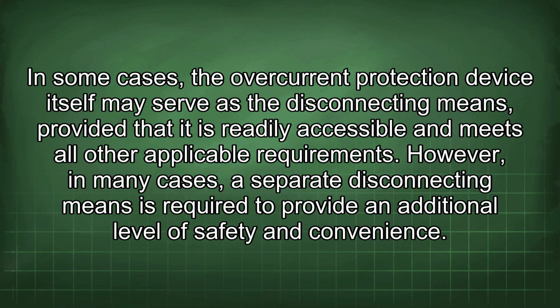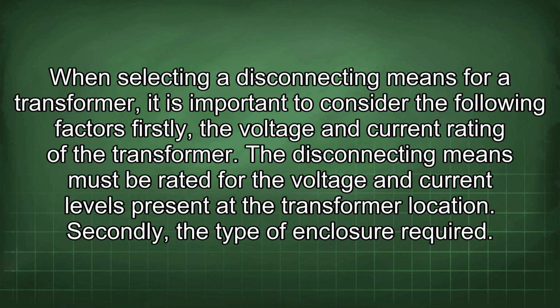In some cases, the overcurrent protection device itself may serve as the disconnecting means, provided that it is readily accessible and meets all other applicable requirements. However, in many cases, a separate disconnecting means is required to provide an additional level of safety and convenience. When selecting a disconnecting means for a transformer, it is important to consider the following factors. Firstly, the voltage and current rating of the transformer. The disconnecting means must be rated for the voltage and current levels present at the transformer location.